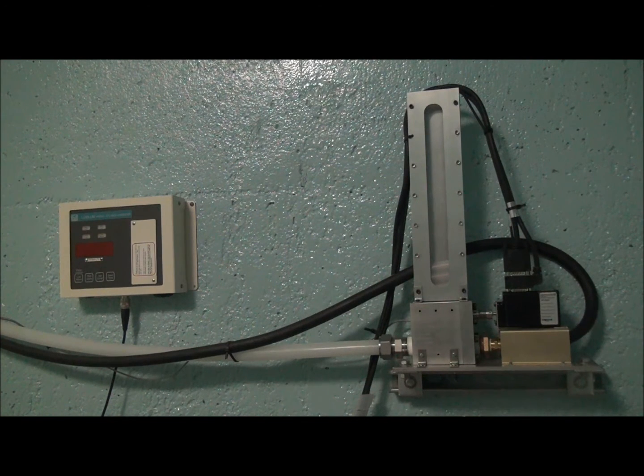Due to the high levels of radiation associated with a neutron generator, the control area, as well as the loading mechanism, need to be located in another room.